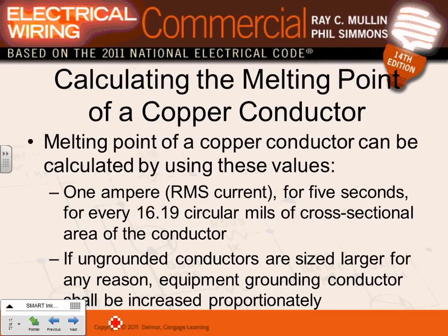If it's insulated, I want you to ignore this number here. This number will get you how much current the copper starts melting. Do you want to wait until the copper melts or before the insulation melts? Okay, so the number for the copper, same thing. I have a 500 kcm THHN, right? Copper. How much current can this conductor carry for 5 seconds?